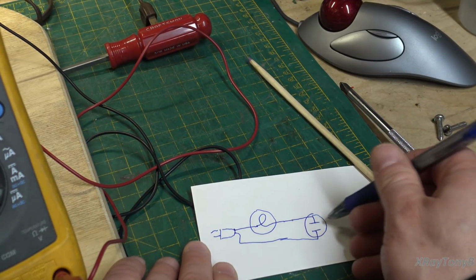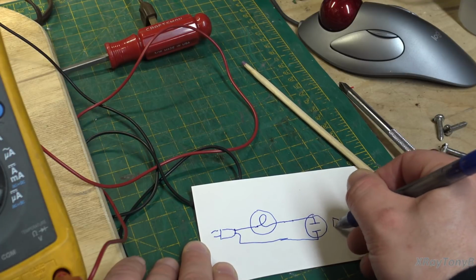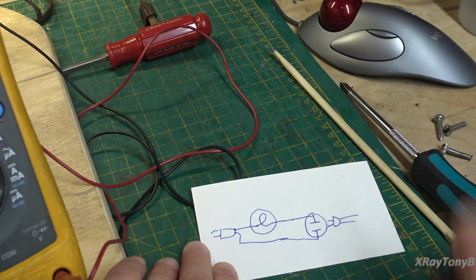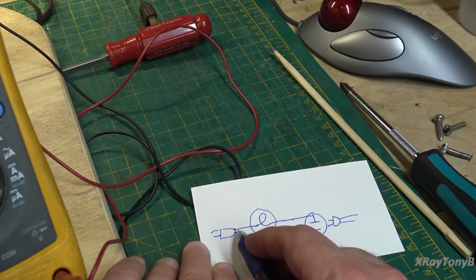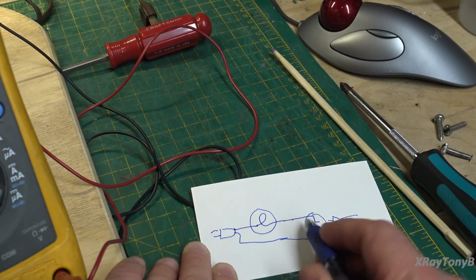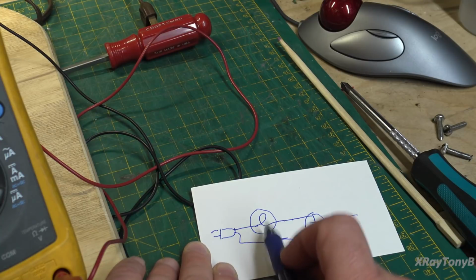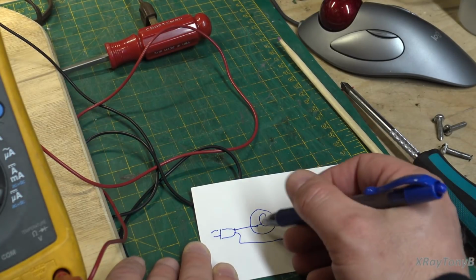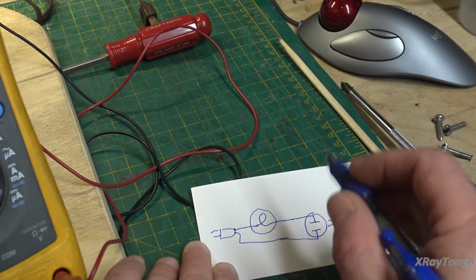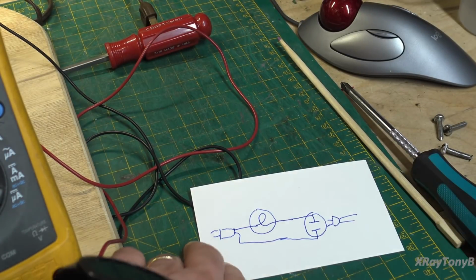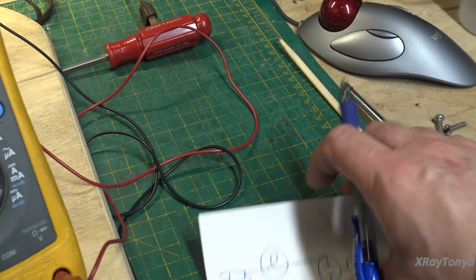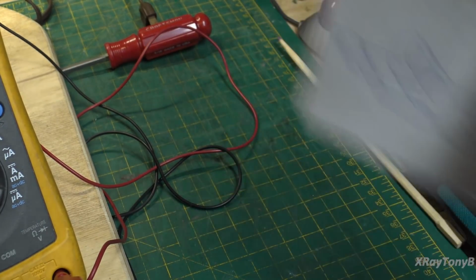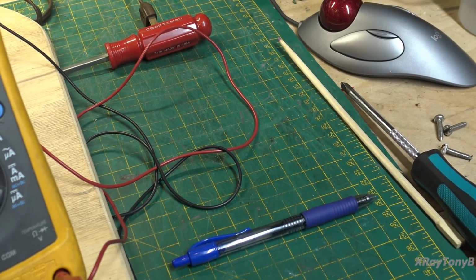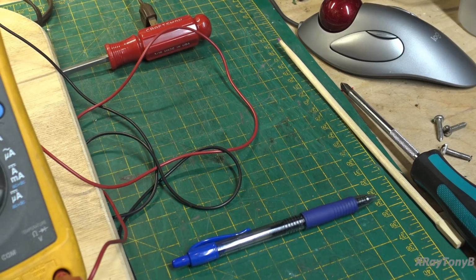So essentially, when you plug your device into that, this light bulb is in series with the device that you're plugging in, and that's going to limit the current. If there's a dead short, the light bulb will light up bright. If there's not a dead short, the bulb will be dim, and that's where the term dim bulb tester comes from. So that's all we have over there. There are many different versions of that, and some people have made some pretty fancy ones, but mine's just a light bulb in a socket.